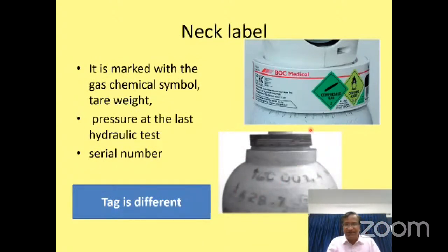Sometimes they put a tag like this, and there will be a green tag. That is different. The tag may be torn and thrown out, and some other tag may be put in its place, but this neck marking is not replaceable, it will have the symbol like this. So the neck should always contain what the gas is.